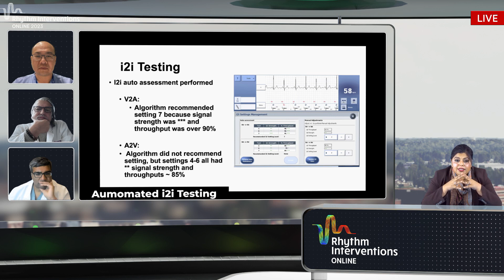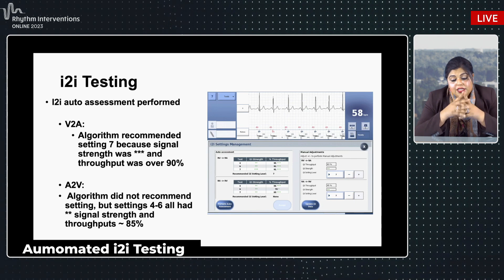And well, this is as we pair the devices, while the tethers are still attached. It does the auto assessment and tells us what signal strength and what throughput we have, and gives us an optimized setting that we could potentially use. In this case, we opted to select some higher throughput values or higher strength, just because it was immediate, and we were still having some null markers that tell us that i2i was not great when the tethers were still attached. So since it was a good implant and we were at a reasonable distance and reasonable i2i, we decided to release the device.